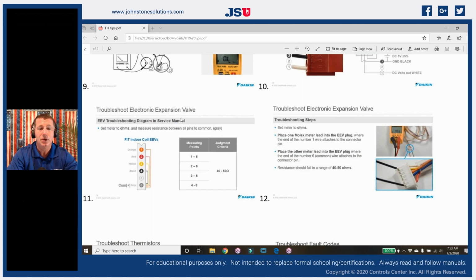So most of the time we find in the field, the electronic expansion valves themselves really don't go bad. The only way an electronic expansion valve will physically go bad inside is if I get a bunch of contaminants in my system. If I didn't flow nitrogen while I was brazing, and if I didn't draw a proper vacuum to get moisture out of the system. That's the only thing that'll cause them to go bad. They're so simple by design. So most of the time, what actually fails is that electronic expansion valve power head. Most of them you're going to find are going to be between 40 and 50 ohms. All of ours are between 40 and 50 ohms. So we're going to ohm out all 4 of our windings, and we're going to see what those look like.